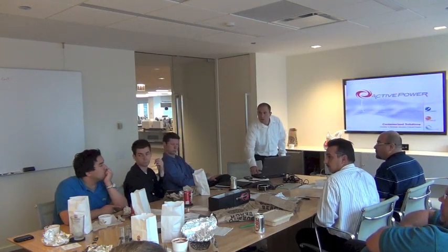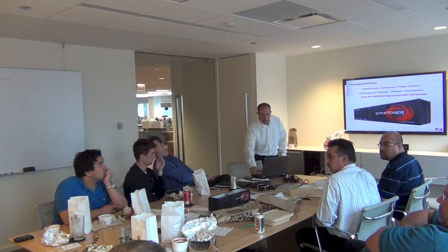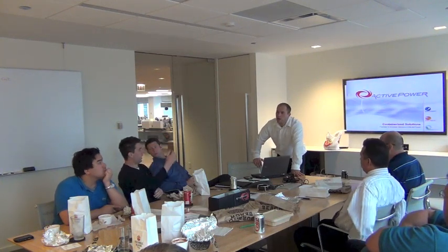Is your inverter ramp time integral to your flywheel runtime? Let's say you're at 22 seconds posted runtime. Does that include 5 or 8 seconds of walk-in? Yeah, and we never walk in the load.